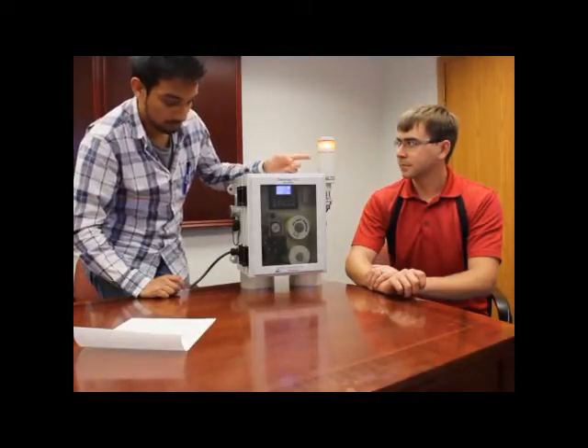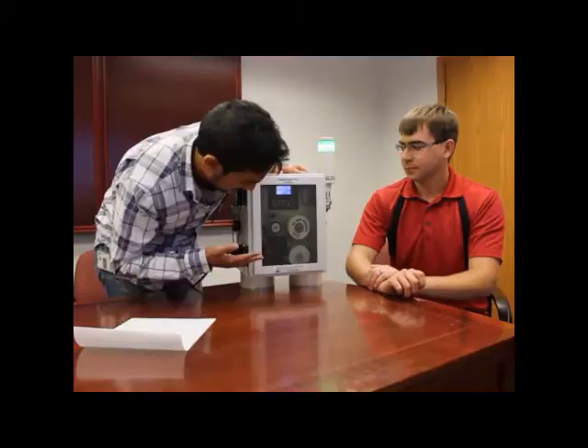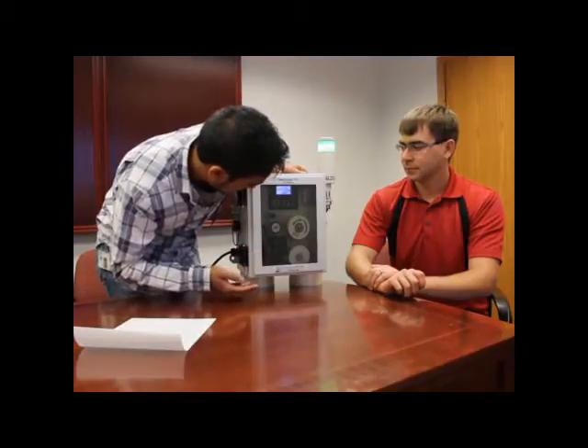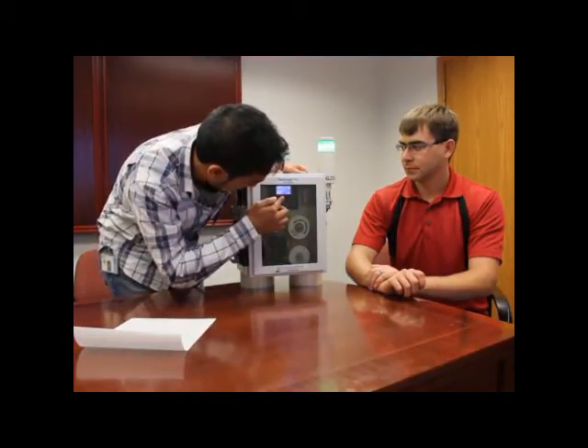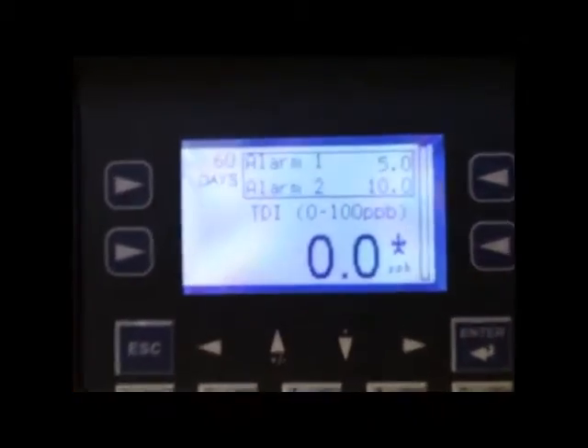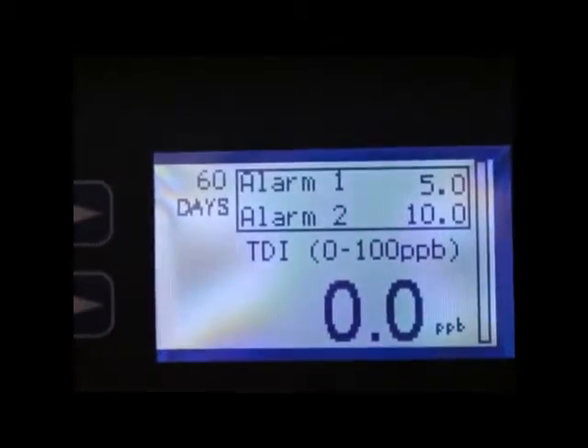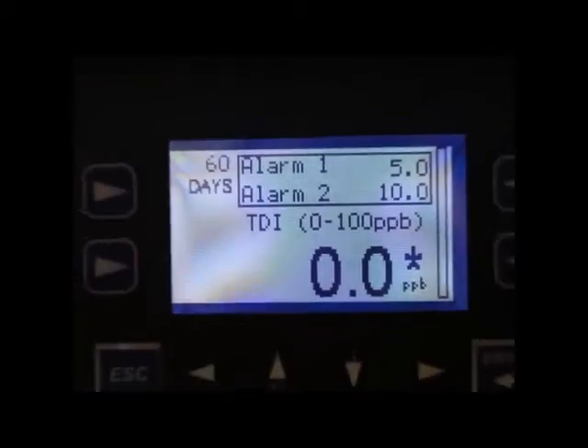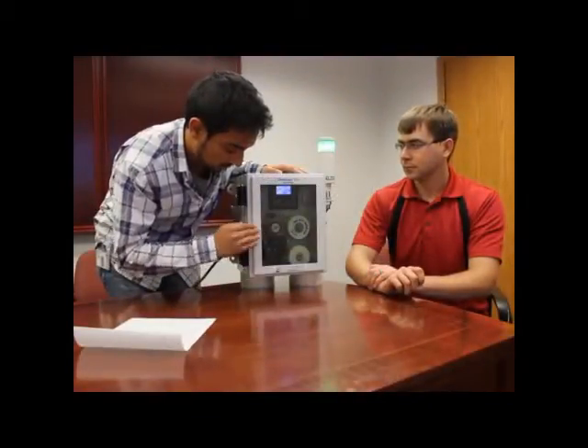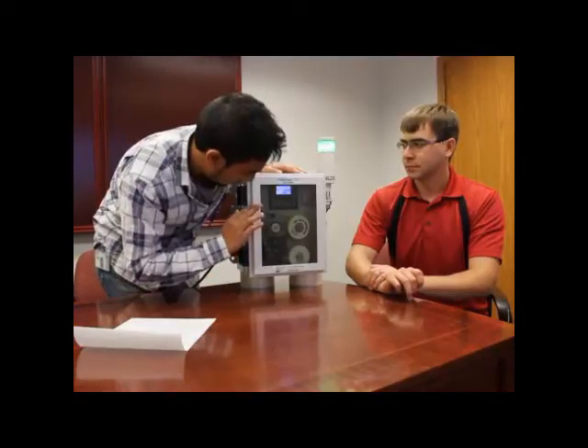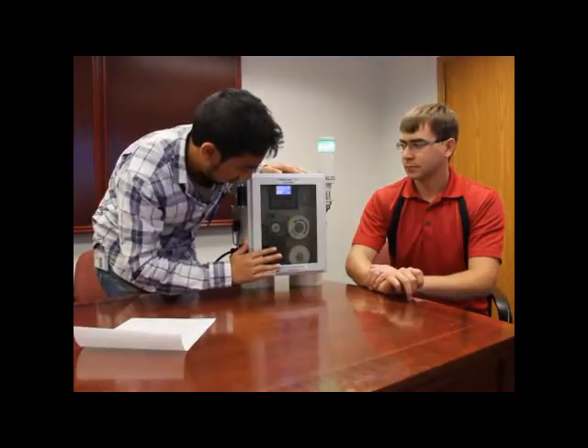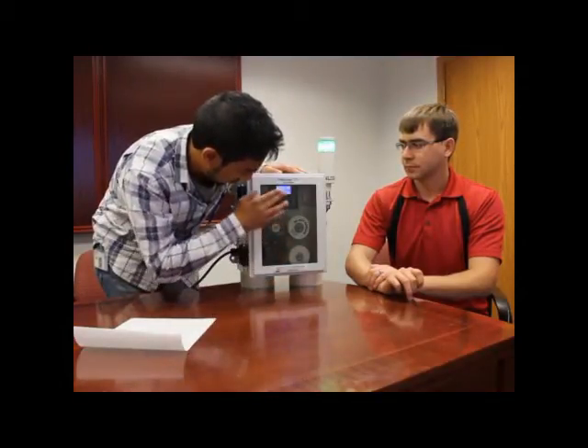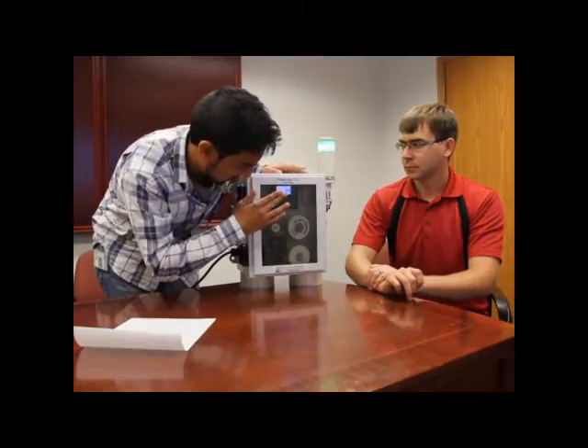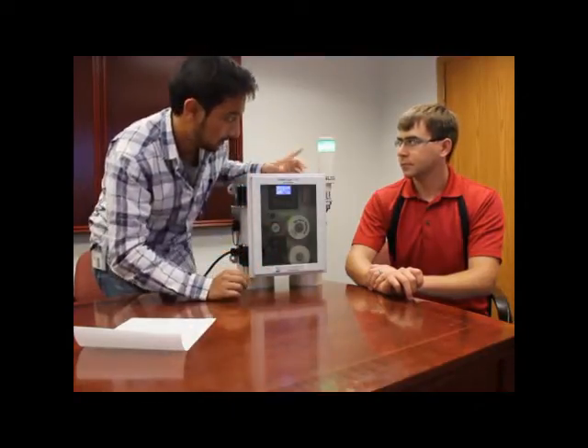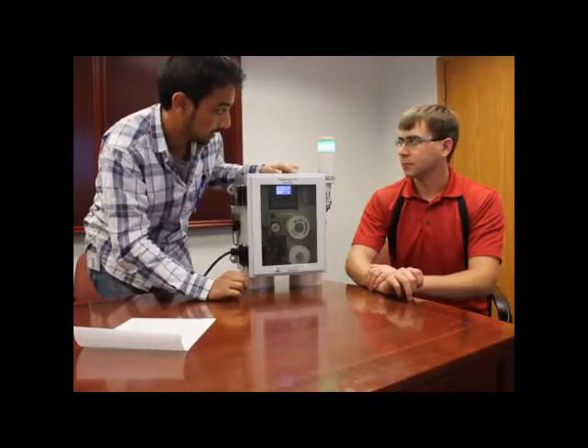It'll be yellow for a bit, but it'll eventually go green. Once the pump starts working, it'll show how much isocyanate's in the area. As of now, we have 0 parts per billion because we're in an office space, so the air going in here is free of isocyanates. If the air is actually contaminated with isocyanates, a number higher than 0 will show up, this light will turn red, and an audible alarm will sound.